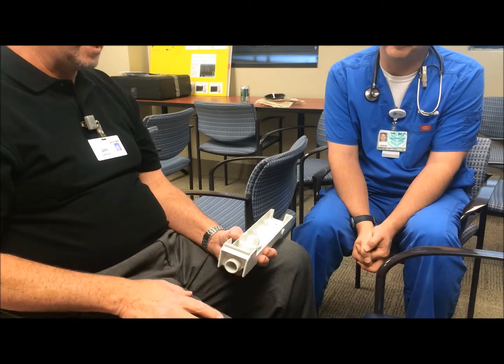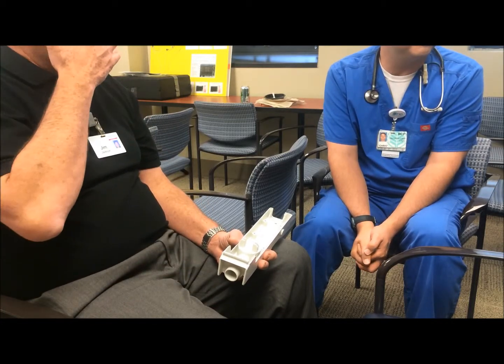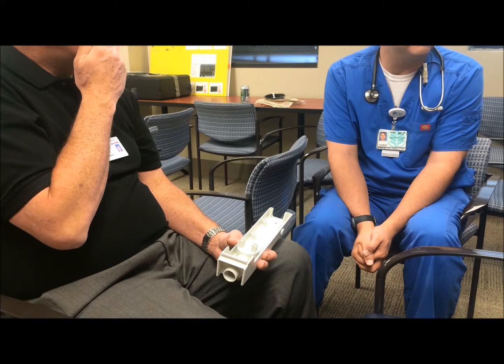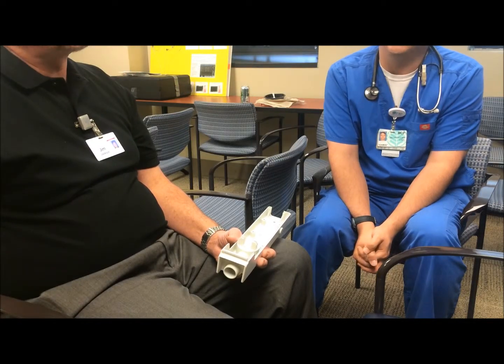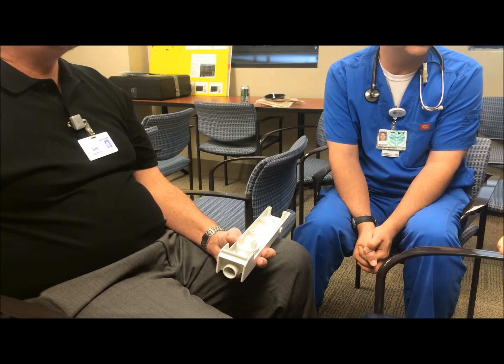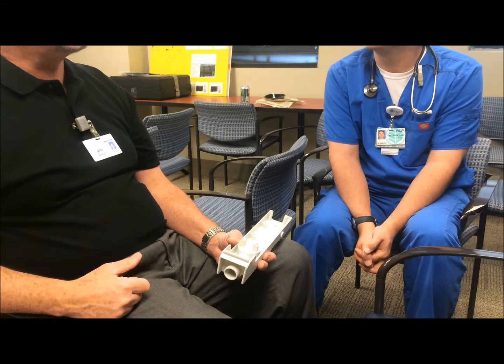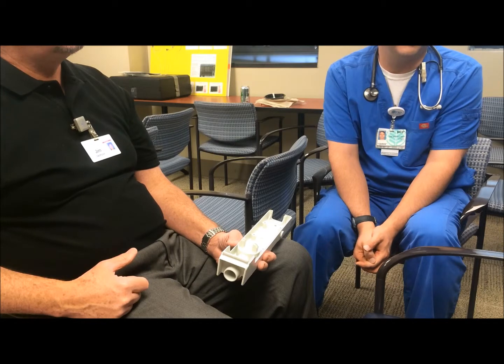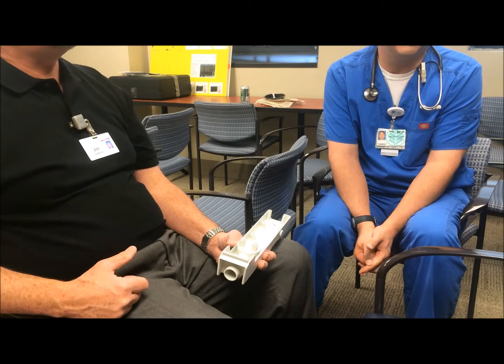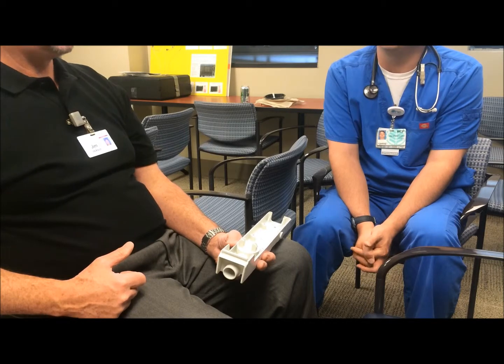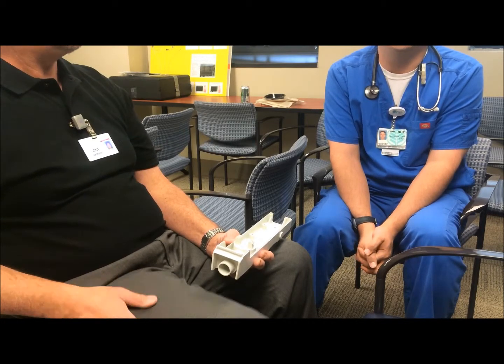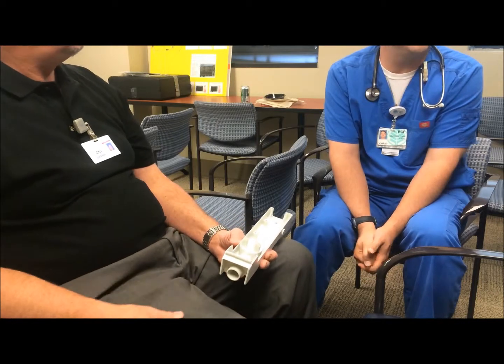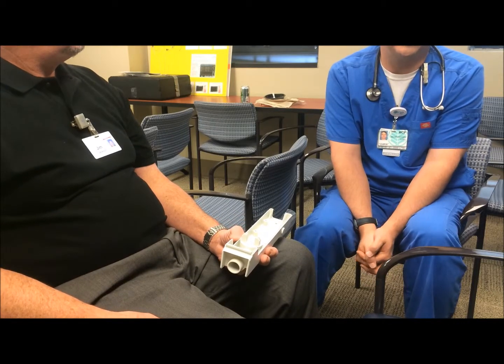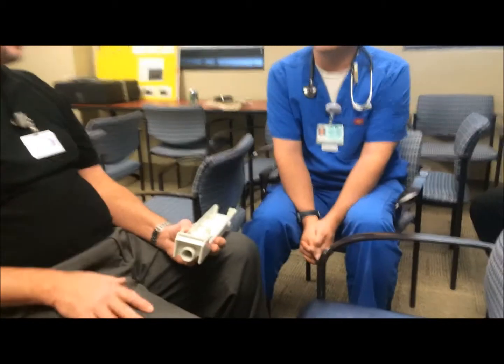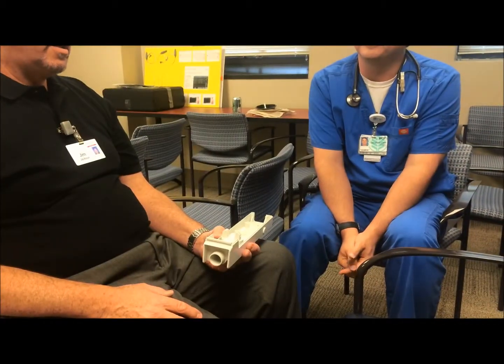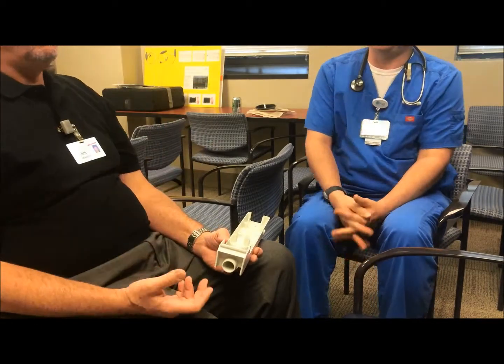They're great nebulizers. I got that at Cleveland Regional. They bought the ultrasounds. The old style ultrasonics or the new ones? That's the older style. It sat out there like a humidifier would. Yeah, and they said they had to do that because that's what RT recommended to go with the machine, and not to use any other type of nebulizer. Really? Yeah, I remember that from back in the day, six or seven years ago. Aerogens are different. It's like a little vibrating mesh, like a T stem. Versus true ultrasonic, they're about the same in terms of functionality. No pressure, it just vibrates the mesh.